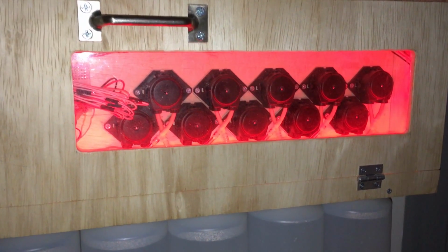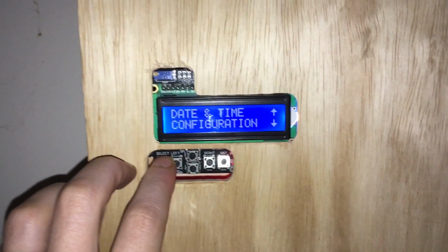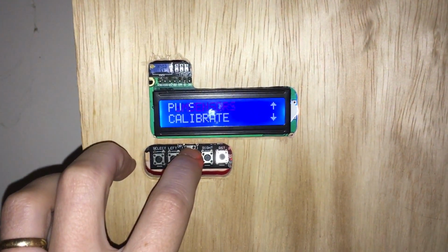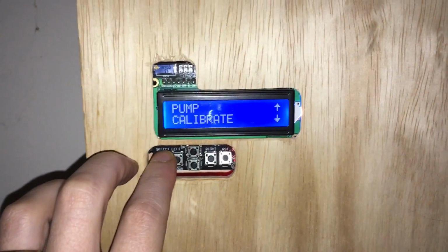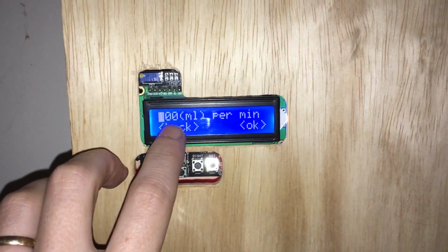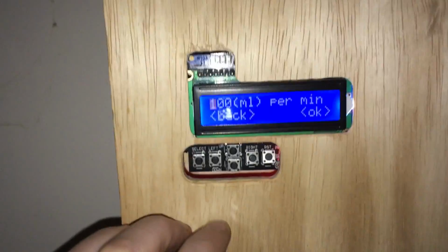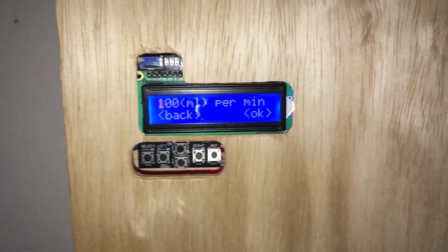To calibrate how many milliliters your pump motors can turn per minute, go into System Settings, Pump Calibrate. Here you get the opportunity to set the amount of milliliters per minute all of your pumps can do. Once done, hit OK.